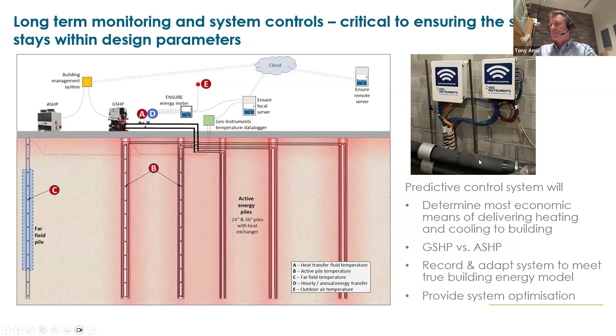There are parts of the year, around this time, that we call shoulder seasons, where the air temperature is potentially warmer or cooler than the ground, and we can work out the most electrically energy efficient way of delivering heating and cooling. That calculation is then sent as a signal to the heat pumps on the roof to operate in the most energy efficient mode.